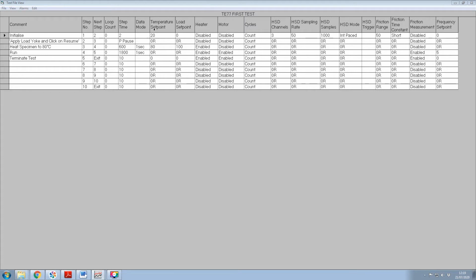The next columns all refer to control parameters, corresponding to all the red box items on the main page 1 screen, including switches and set points. There are also columns for programming high-speed data acquisition, in other words, the red box functions on the page 2 screen. In this example, the first step is used to set up some starting parameters before set point controlled devices are enabled. The temperature set point has been set to 20 centigrade, so that when the heaters are enabled, there is not a large difference between the set point and the ambient temperature.